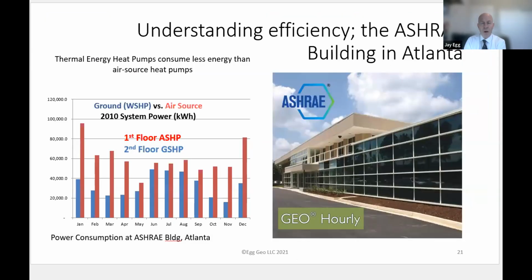The reason this is so important is because as we convert from combustion heating to electric heating and cooling, we find that electric heat pumps that are air source require a lot more peak energy consumption in the wintertime than geothermal heat pumps. In the ASHRAE headquarters, which is the American Society of Heating, Refrigeration, and Air Conditioning Engineers, which is actually a worldwide society, as I'm sure everybody listening to this realizes, they installed air source heat pumps in their headquarters in Atlanta, Georgia, US, in 2010, on the first floor air source and on the second floor ground source.